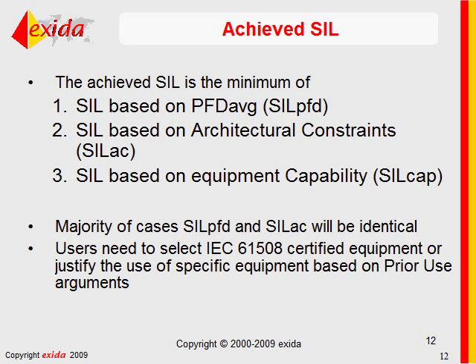Design verification basically requires that we meet 3 barriers. I like to think of them as 3 fundamental requirements. Number 1, we must meet a probability of failure on demand, PFD average, or we cannot exceed a maximum probability of failure. If we do, the design is not safe enough.